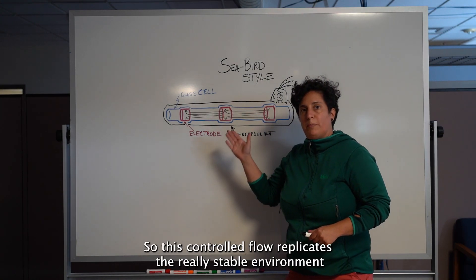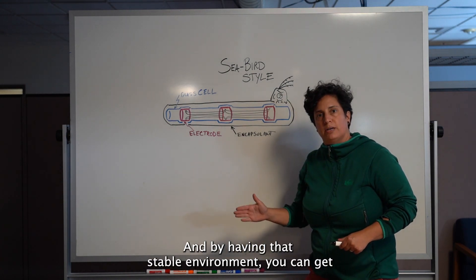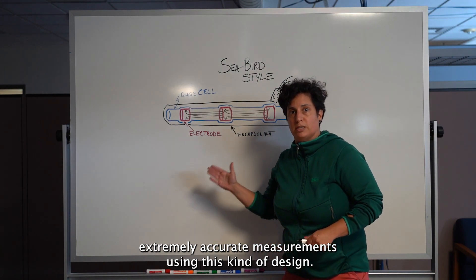So this controlled flow replicates the really stable environment of a calibration bath. And by having that stable environment, you can get extremely accurate measurements using this kind of design.